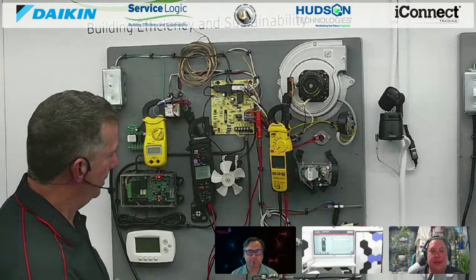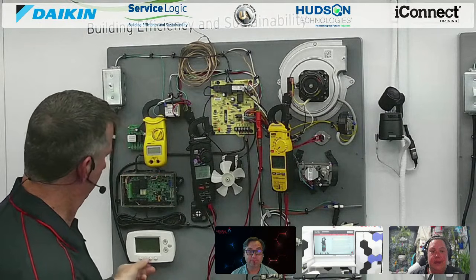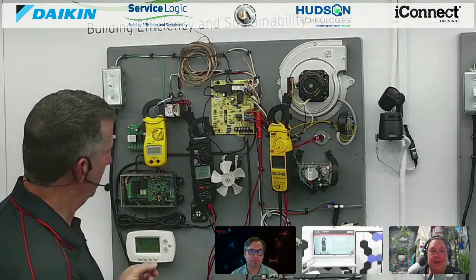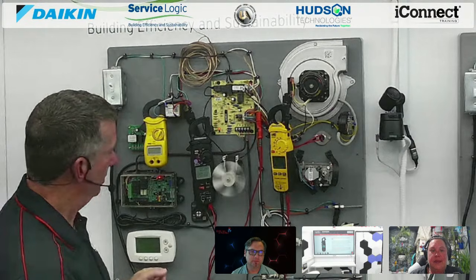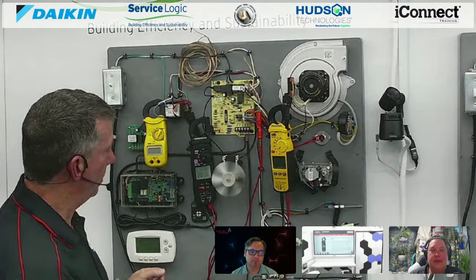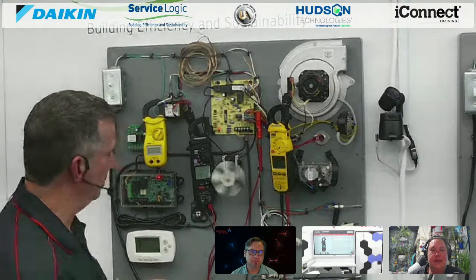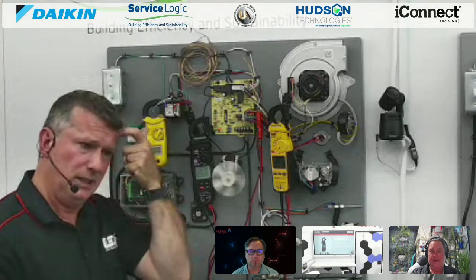Oh, we're actually picking up even more now. Yep, turn a fan on. So I'm picking up about 2 volts AC, and remember, I'm not generating anything. I'm simply inducing voltage from my AC line into this additional wire, which could have been a control wire, a high voltage wire not being energized, or a common. There's a variety of different wires it could have been that we'd be inducing a voltage onto.